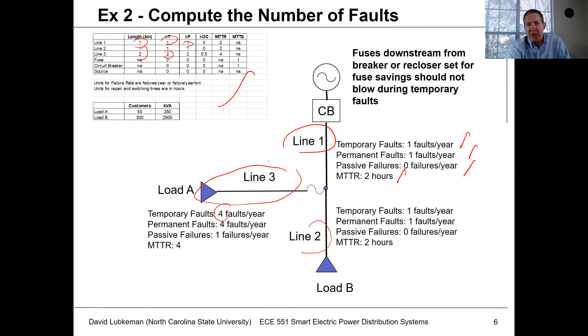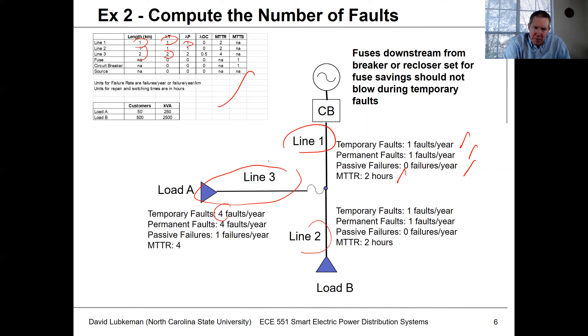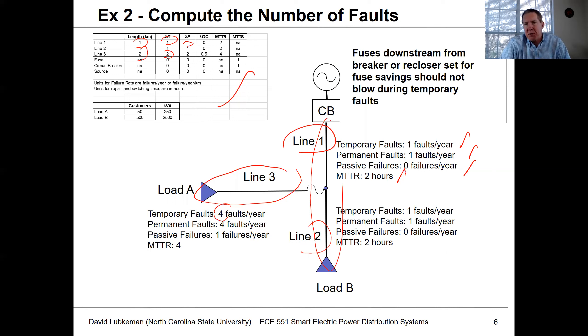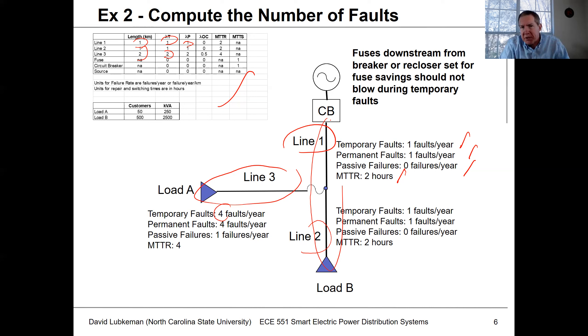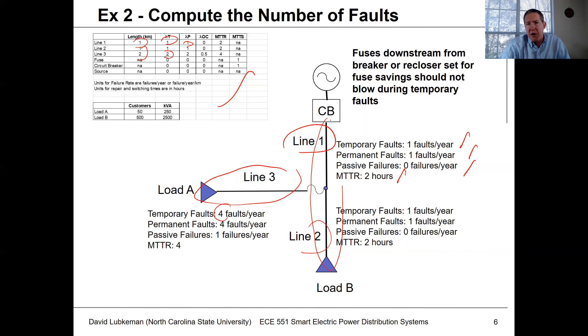This is typical of what you'd actually see on distribution circuits — we typically have more failures on tapped laterals. A tapped lateral serving a residential area is more difficult to keep clear of trees because these lines snake in and out on residential streets. So it's not unusual for taps to have these higher failure rates.